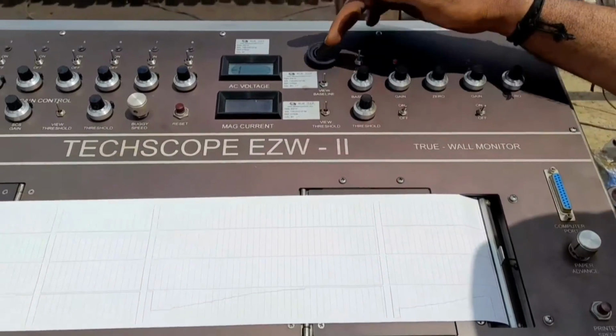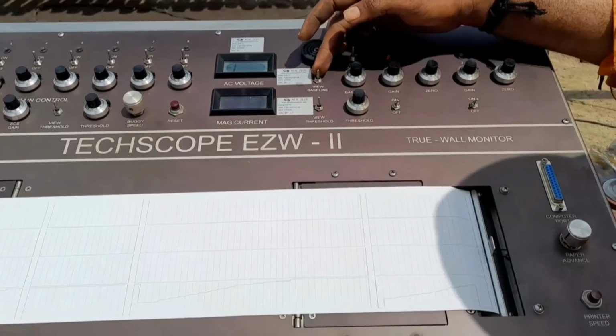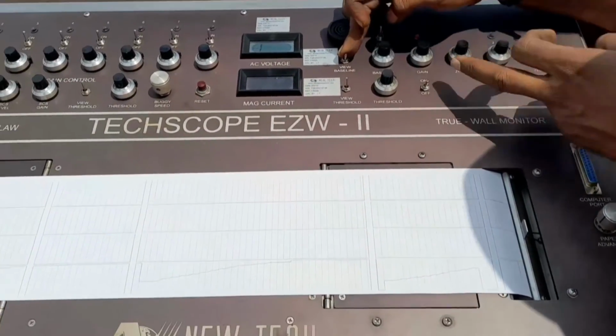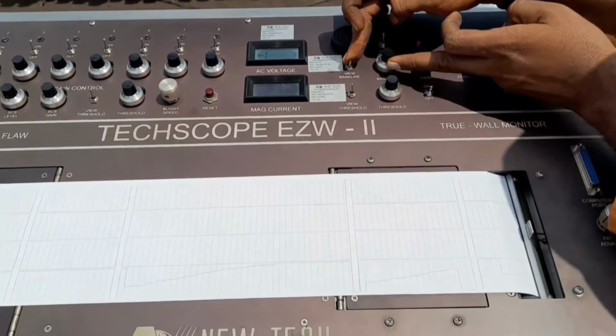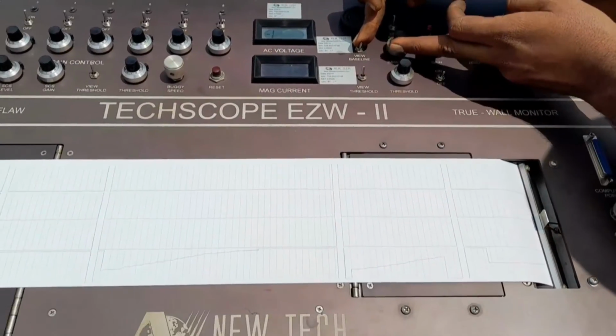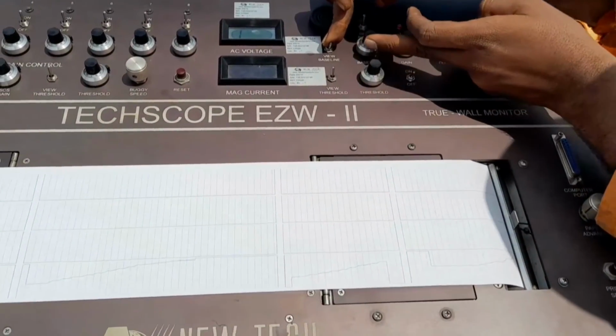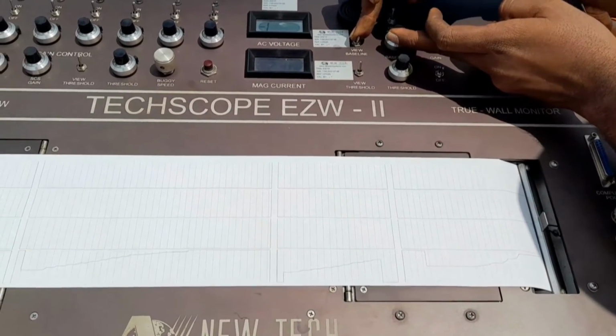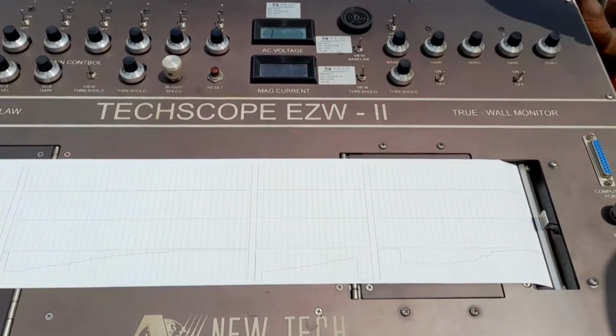Before starting the wall monitoring setup, you have to align all the shoes. Don't place the buggy head on the wall loss area. Then switch on the mag, hold the baseline toggle switch, run the printer. This time mag is on, printer is on. Then adjust the value 1 mm or 2 mm from top. Then your baseline is okay.